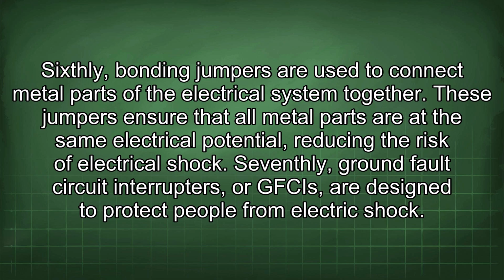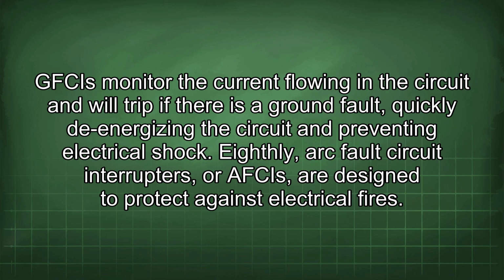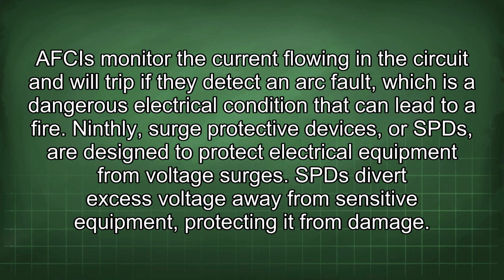Seventhly, ground fault circuit interrupters, or GFCIs, are designed to protect people from electric shock. GFCIs monitor the current flowing in the circuit and will trip if there is a ground fault, quickly de-energizing the circuit and preventing electrical shock. Eighthly, arc fault circuit interrupters, or AFCIs, are designed to protect against electrical fires. AFCIs monitor the current flowing in the circuit and will trip if they detect an arc fault, which is a dangerous electrical condition that can lead to a fire.